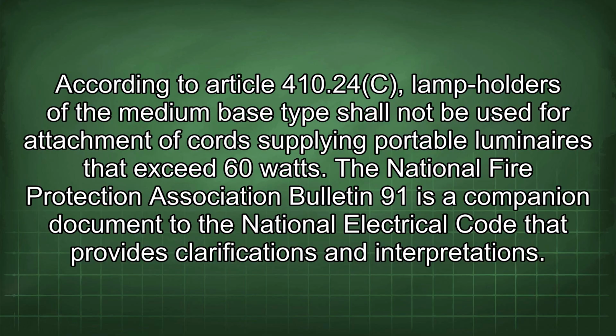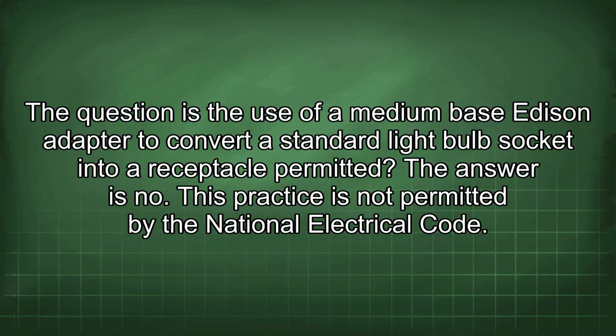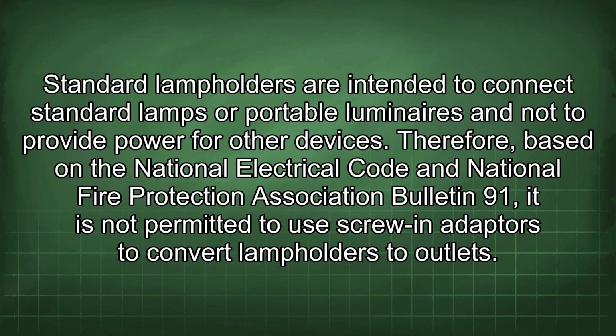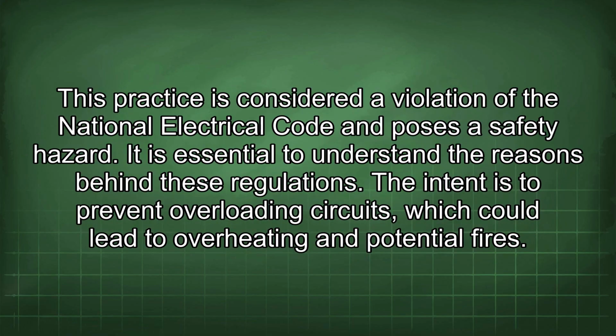exceed 60 watts. The National Fire Protection Association Bulletin 91 is a companion document to the National Electrical Code that provides clarifications and interpretations. The question: is the use of a medium base Edison adapter to convert a standard light bulb socket into a receptacle permitted? The answer is no. This practice is not permitted by the National Electrical Code. Standard lampholders are intended to connect standard lamps or portable luminaires and not to provide power for other devices. Therefore, based on the National Electrical Code and National Fire Protection Association Bulletin 91, it is not permitted to use screw-in adapters to convert lampholders to outlets. This practice is considered a violation of the National Electrical Code and poses a safety hazard.